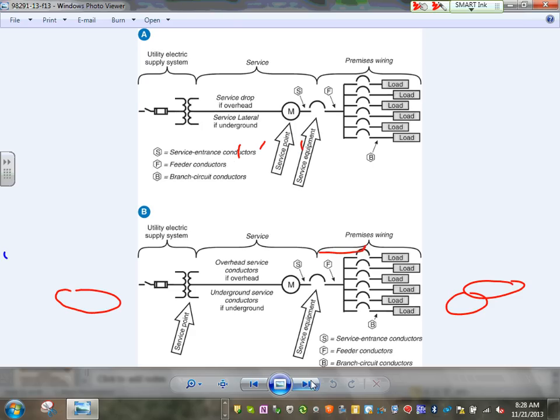Okay, moving into when you bring, this is the most important thing. We did this one in the residential, if you guys remember. We said this is called the service point. The utility, this is called the service point, underground or overhead. That's your service point. The conductors, if you come from overhead, are called overhead conductors, or underground service conductors, or service laterals, or service drop into the meter. From the meter into the first disconnect, this one, it's called service entrance conductors. From this one into the building, it's called feeders. So that's the terminology that the NEC code uses.